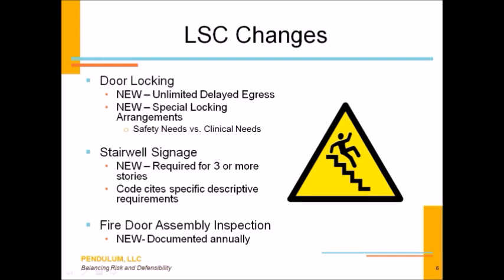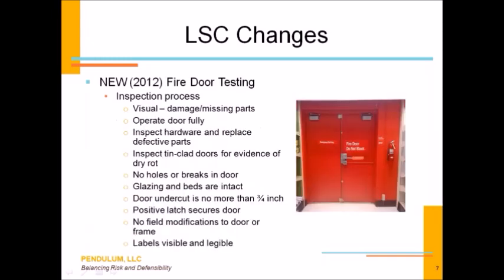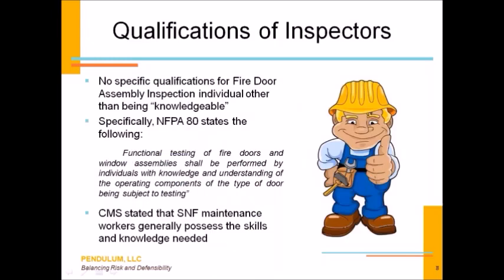One of the newer requirements that's been a heavy lift for providers in healthcare, particularly nursing homes and hospitals, especially if you haven't been doing this all along, is a process known as a fire door assembly inspection. This is a new documented process that has got to be done annually. It needs to be documented, and it's got to be done by a qualified person. So you might think, what's the big deal? We look at our doors regularly. We might be doing a monthly, maybe even a weekly check, but this is a comprehensive assessment of a door that looks at multiple elements. You see on the screen right now some of those elements that are illustrated, but you've got to make sure that you're doing a comprehensive annual documented fire door assembly inspection of your fire doors in your facility.